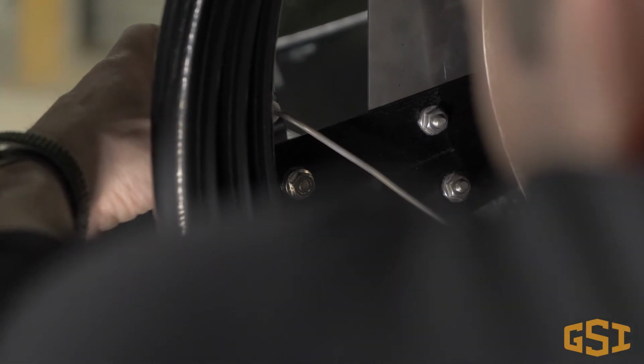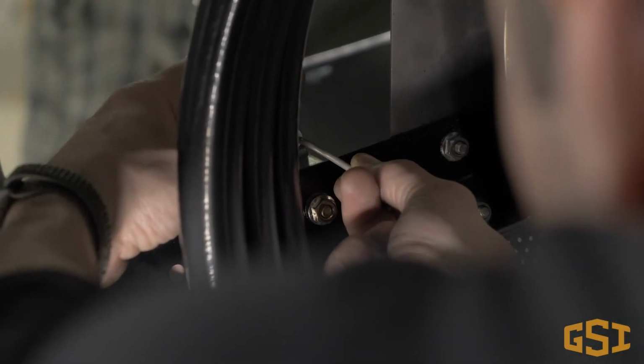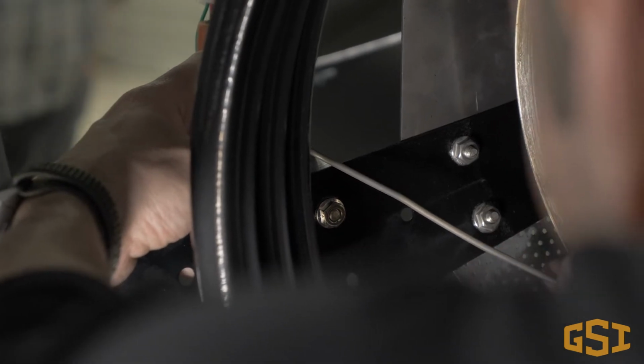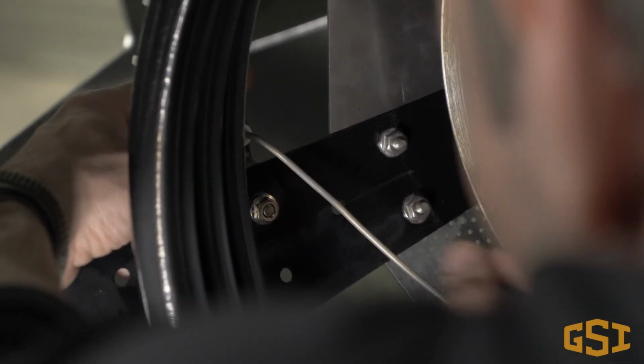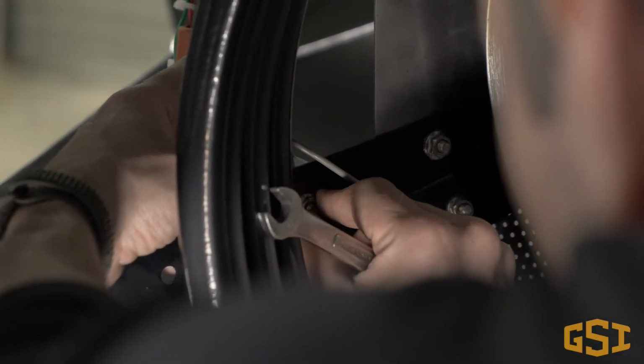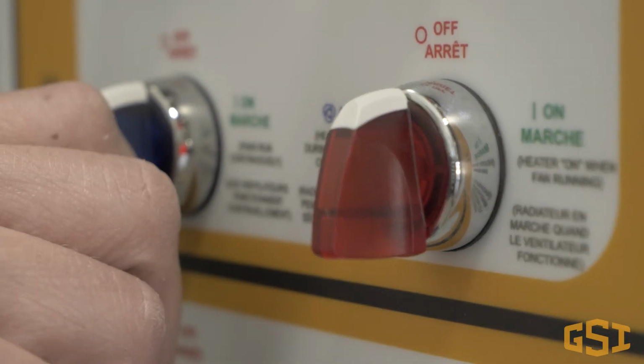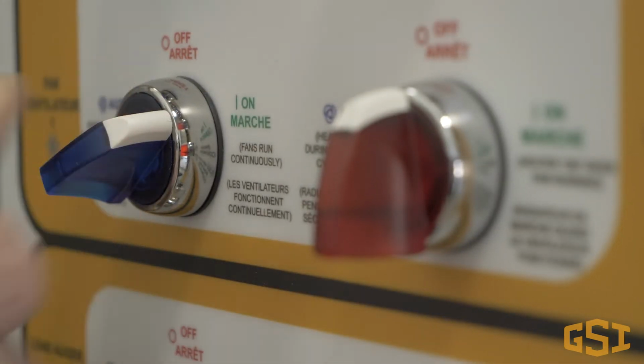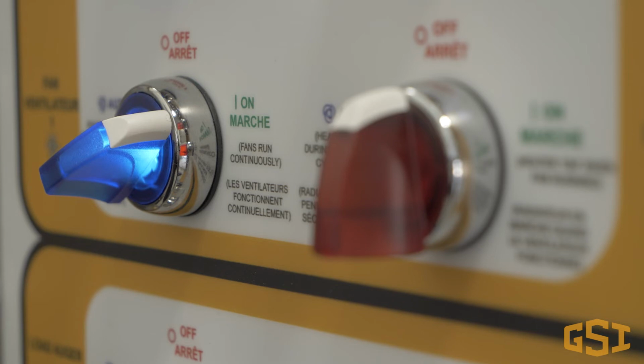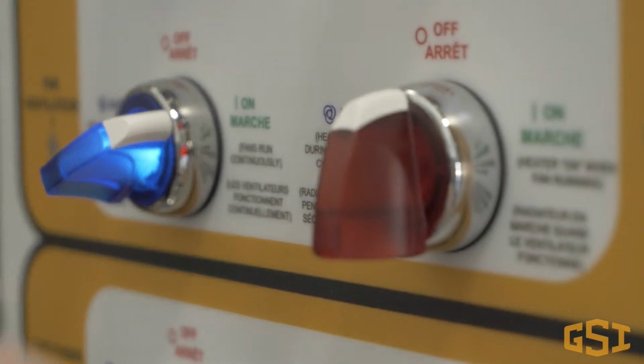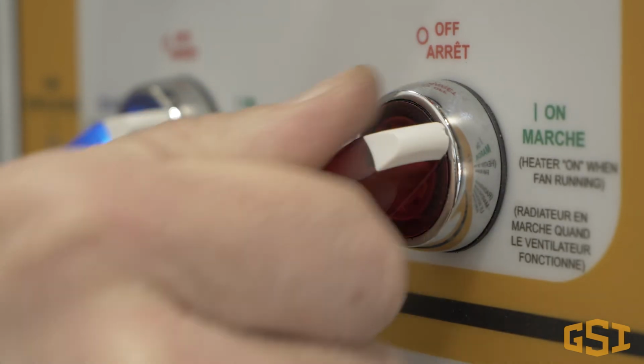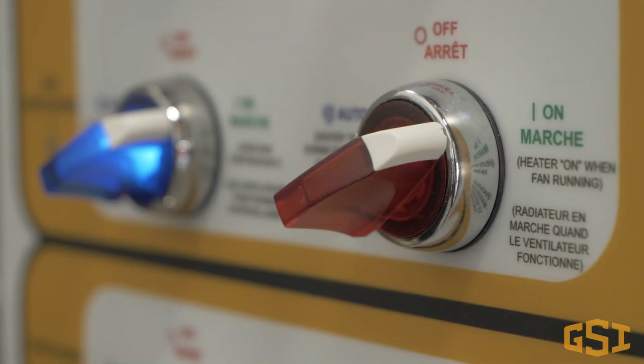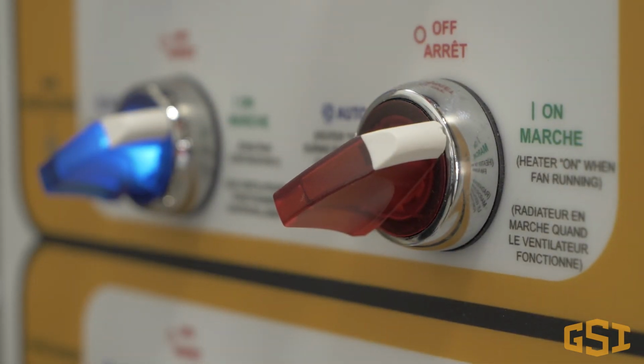If you are still experiencing loss of flame failure, the next step is to ensure the flame probe is located in a place where it is constantly in contact with the flame. GSI manufactured dryers with vision controls have a unique feature that informs you when flame is detected. Each burner switch on the vision control panel has a light in the center. The light is used to inform the operator when a flame is detected.